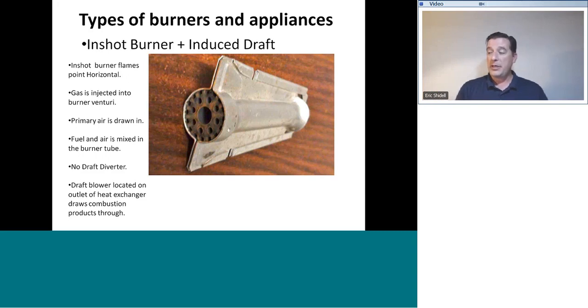Here is our burner itself. Here is the business end of that burner. Gas is injected down the other end. You see the open mouth of the venturi here drawing air to mix with the gas. As it travels through the burner tube, the air and the fuel are mixed and come out to be a flame down on the end.